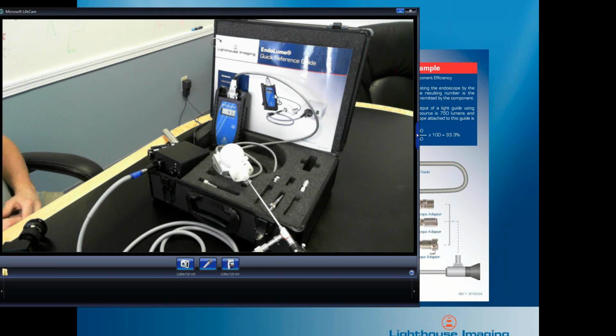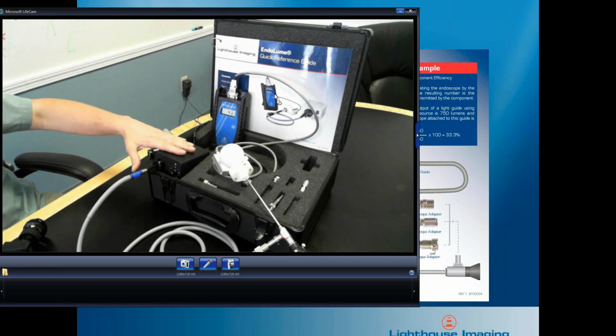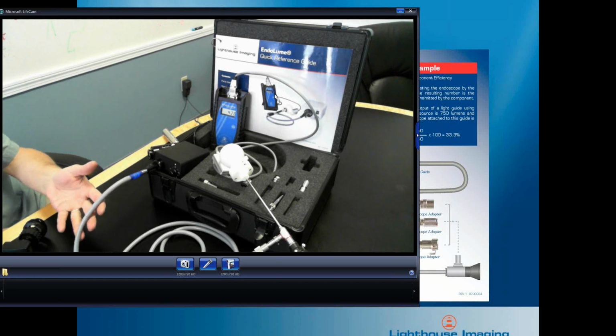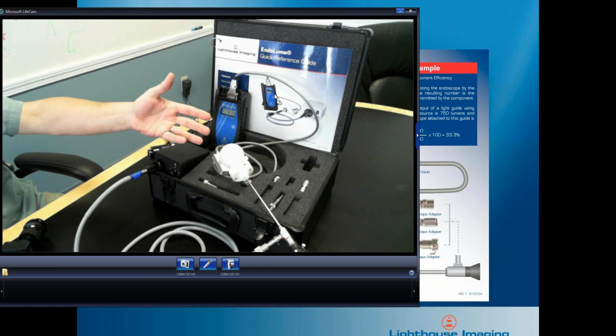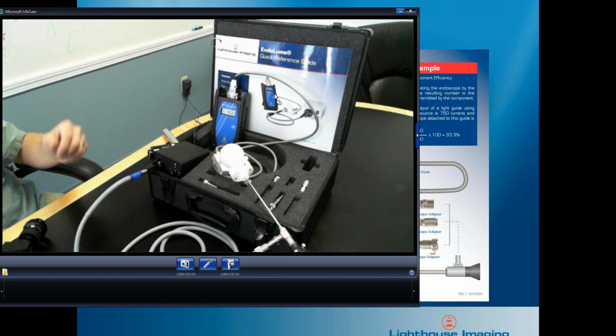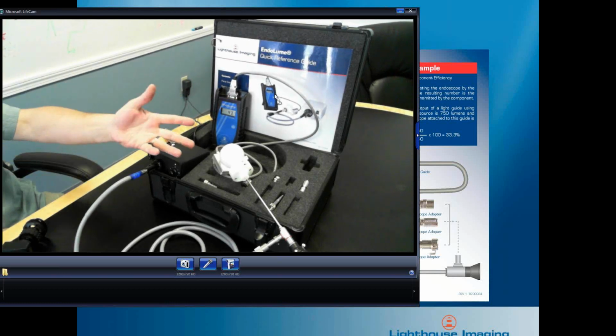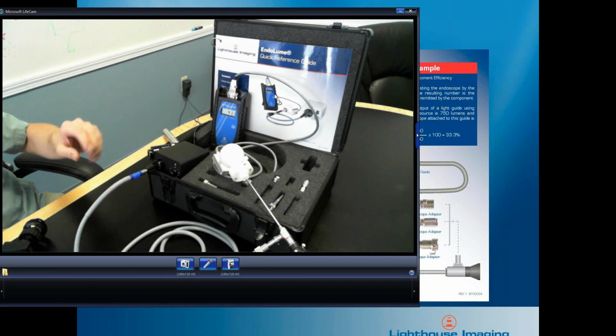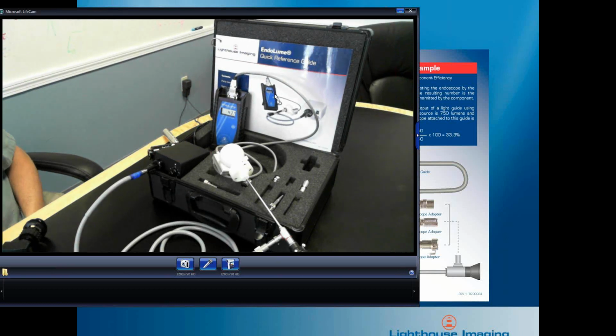So the possible cause of problem is on the scope, is that? Yes, yep, absolutely. We checked. That is a great question, because that's exactly the point of using the EndoLume. We've now confirmed that the output of the light source is good. We've confirmed that the transmission efficiency of the cable is very good. Therefore, yes, if we were to have a dim image problem, it is definitely isolated with the scope. And we see in our test data that this scope is right on the edge of acceptable. Okay. Good.